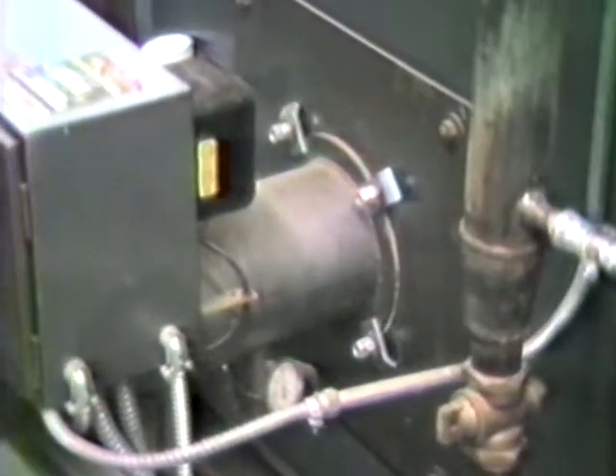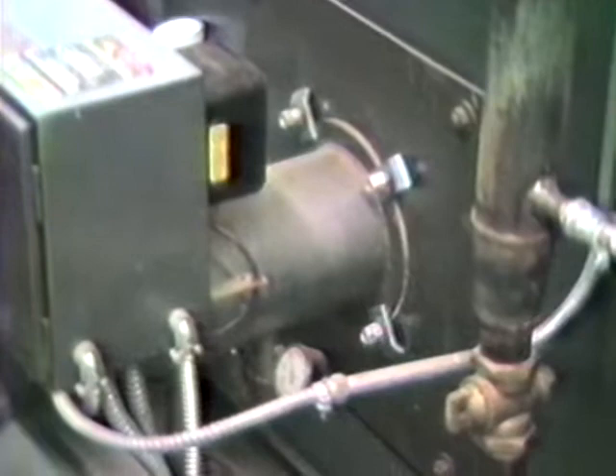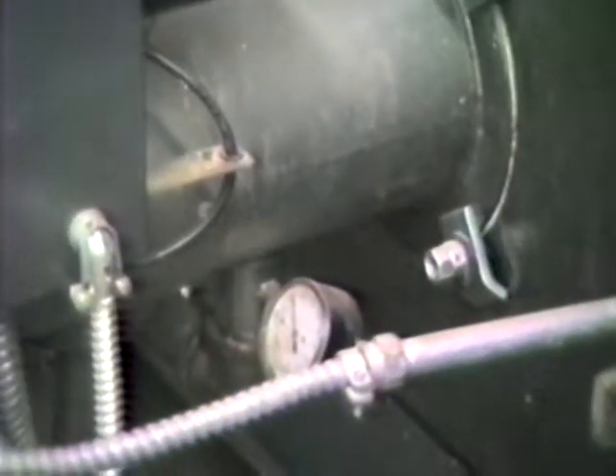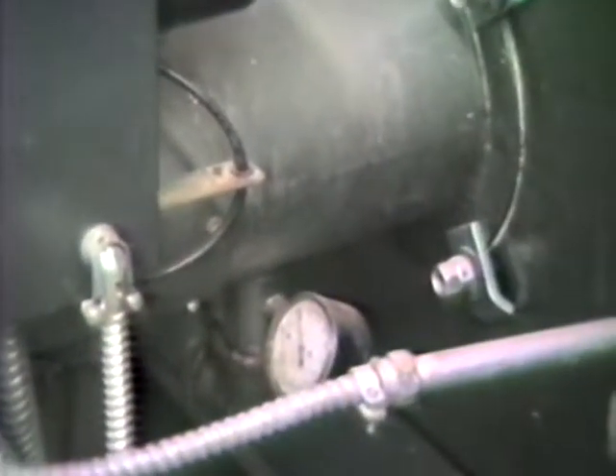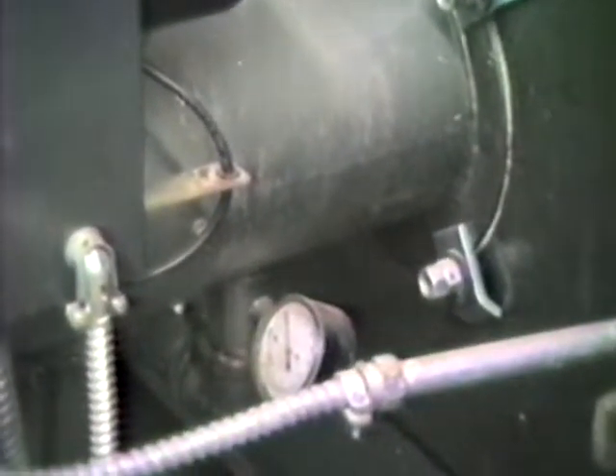There's another gauge that we need to point out on these boilers. Each one of them has a gas manifold pressure gauge. Kind of getting that right in the middle of our screen there. This registers in inches of water column, and we've adjusted the burner fire to be approximately between 2.5 and 3 inches.